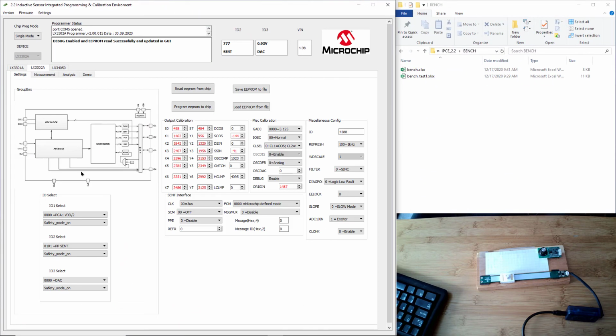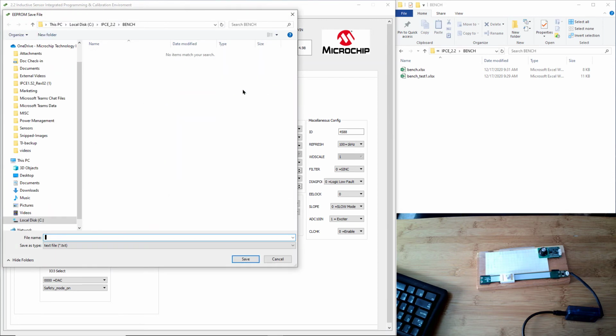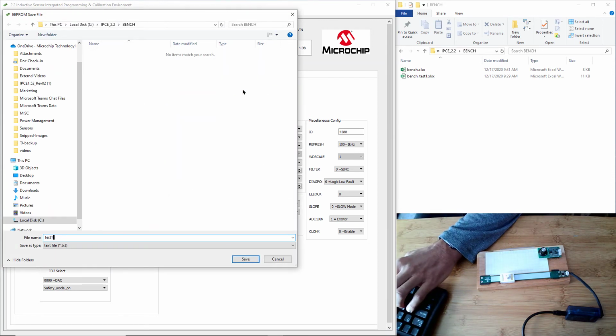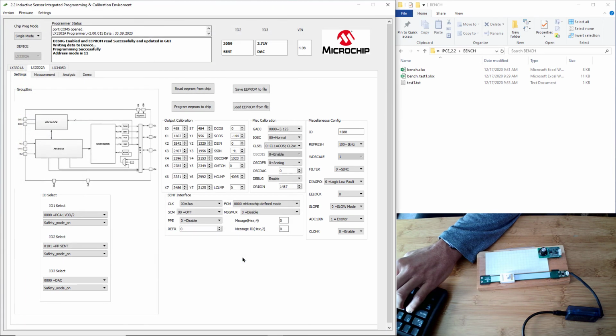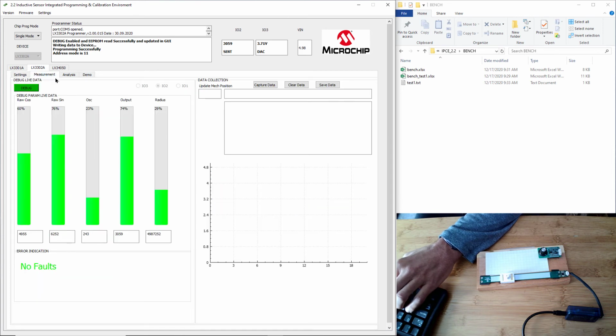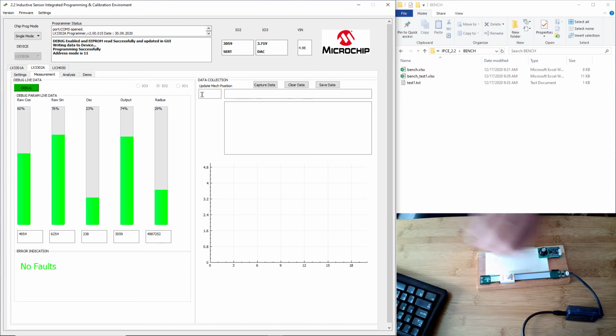We hit the update IC settings. That brings it over to the settings page and takes all those calibration points, and they've turned red in this location. You can see the origin got adjusted, and now we hit the program EEPROM parameter to chip, and then the chip is done. The chip is programmed. We're also going to save this so that we don't lose those EEPROM values on our computer, even though they're on the IC itself, in case it gets overwritten in the future. Now we're really done here, but let's go back to the measurement tab and check a few things.